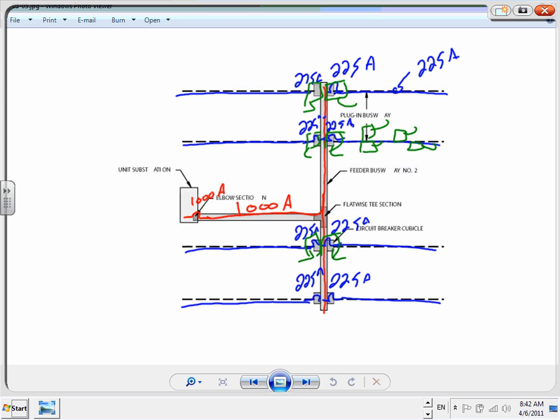Then you're going to put disconnects for the equipment, and the disconnect is going to have an amp load on it, and you're going to circuit the disconnect to the plug-in 225. Each one of these disconnects will be circuited to the plug-in, and then the plug-in will be circuited to the feeder busway, the 1000. The 1000 and the plug-in are going to have a distribution system. You know how to do it, it's like a panel: assign a distribution system for it. And then the 1000 amp will be circuited to the switchgear. Did you guys see how circuiting in Revit we're going to do it? We start by circuiting the disconnect to the plug-in, then the plug-in to the 1000 amp feeder, and the 1000 amp feeder to the switchgear. Any questions about circuiting in Revit? Very easy, straightforward, Revit-wise anyway.